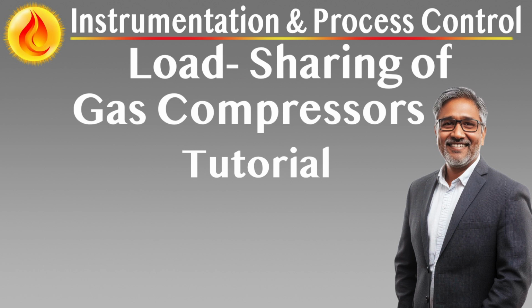Dynamic load balancing. All anti-surge controllers calculate real-time surge proximity DV. Load-sharing controllers use the worst-case DV as a reference and compare it to the network average. The resulting difference is used to bias control outputs so that all compressors remain equidistant from their surge limits. Prevents premature recycling of one unit and ensures mechanical longevity across the train.